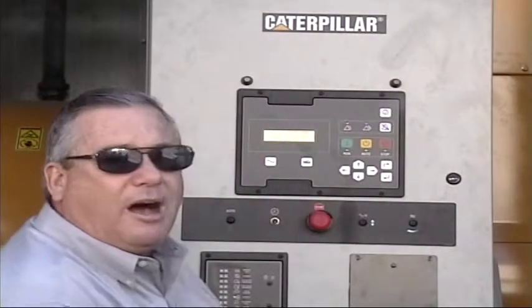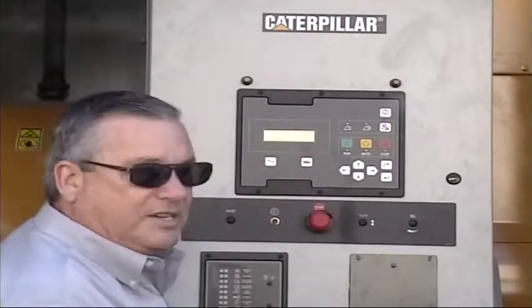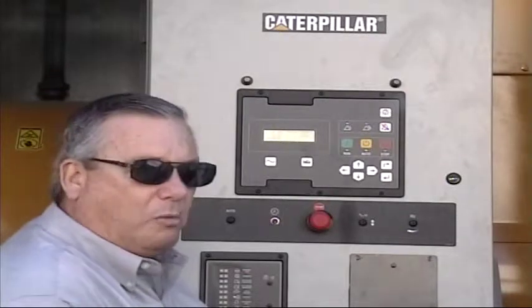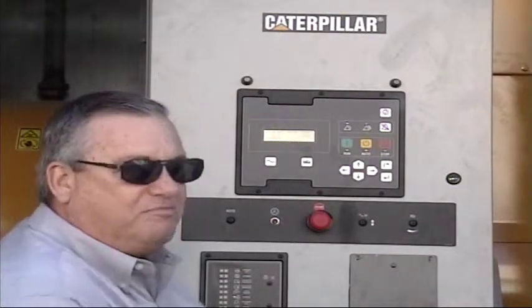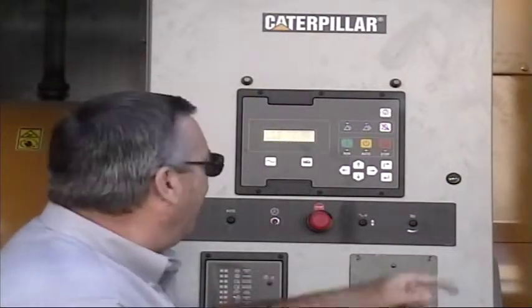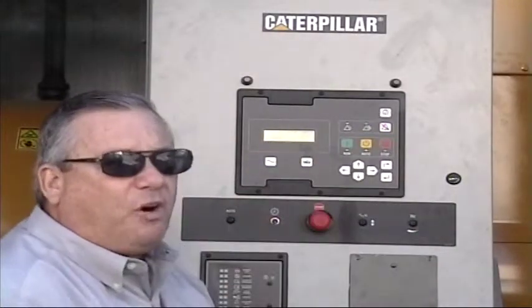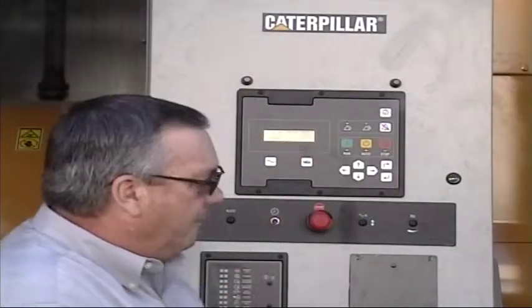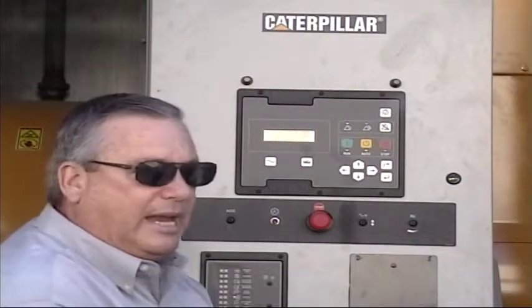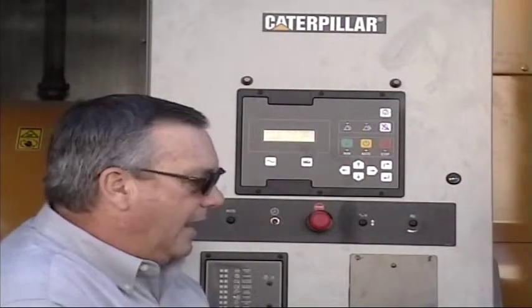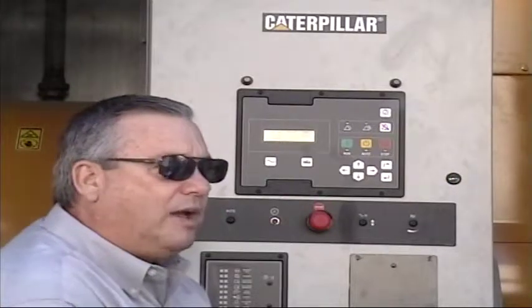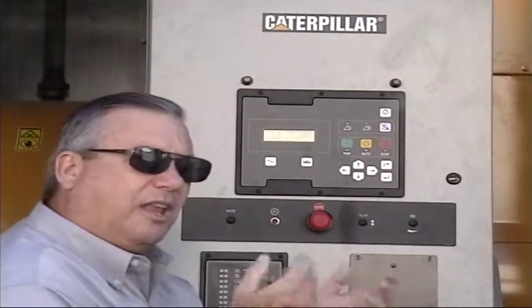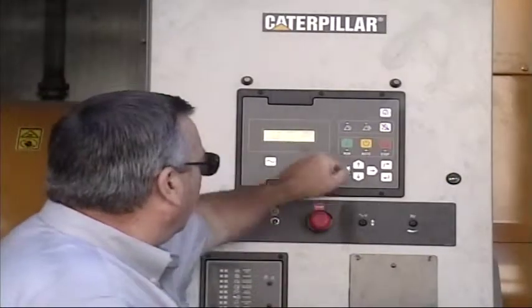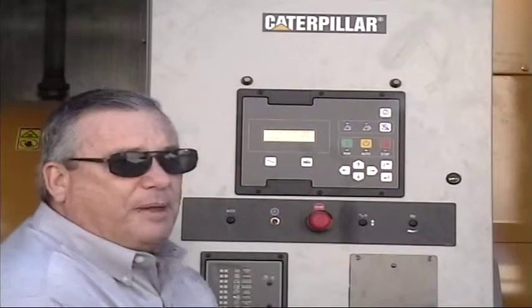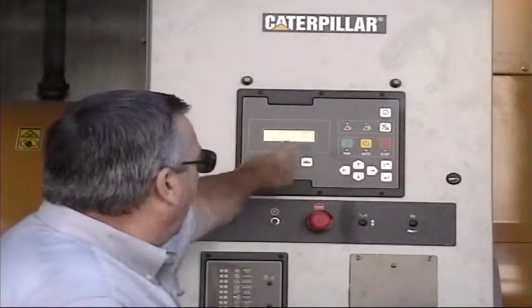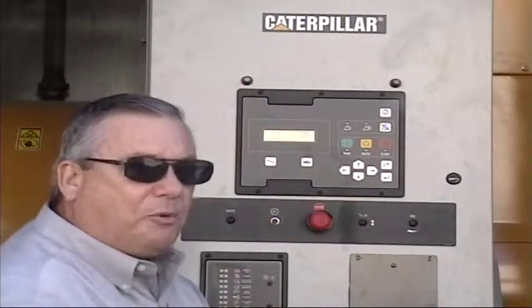Water temperature right now is 111 degrees, so we know the block heater's working, although on a day like this it'll probably show 111 just from the engine. 25.3 volts on the NiCads. The NiCad batteries are in the cabinet here, and Eddie's going to go ahead and do that part when we get to it, but the NiCad charges at a little higher rate, so we're going to see a little higher voltage here. RPM is 1800, showing 0 now because we're not running.